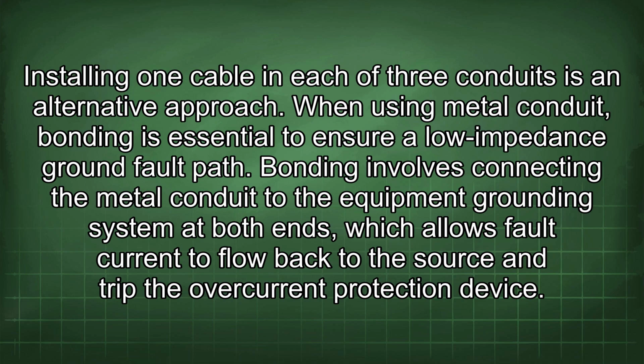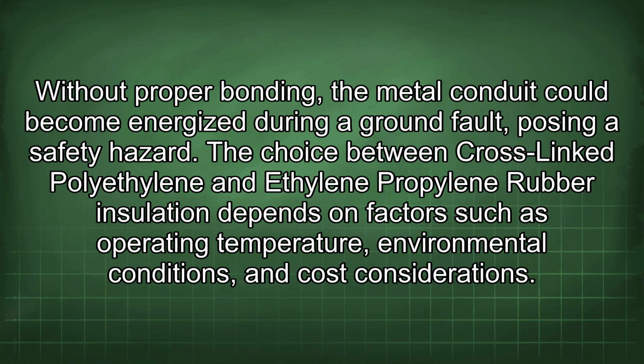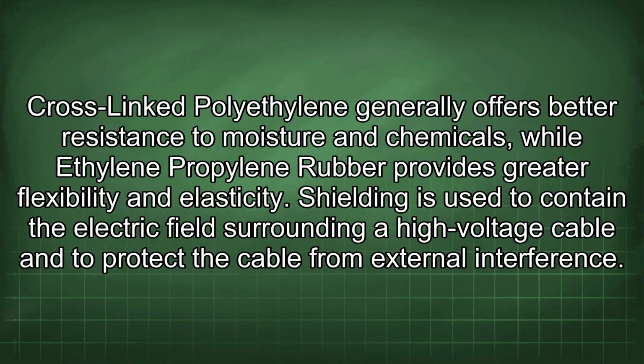When using metal conduit, bonding is essential to ensure a low impedance ground fault path. Bonding involves connecting the metal conduit to the equipment grounding system at both ends, which allows fault current to flow back to the source and trip the overcurrent protection device. Without proper bonding, the metal conduit could become energized during a ground fault, posing a safety hazard. The choice between cross-linked polyethylene and ethylene-propylene rubber insulation depends on factors such as operating temperature, environmental conditions, and cost considerations. Cross-linked polyethylene generally offers better resistance to moisture and chemicals, while ethylene-propylene rubber provides greater flexibility and elasticity.